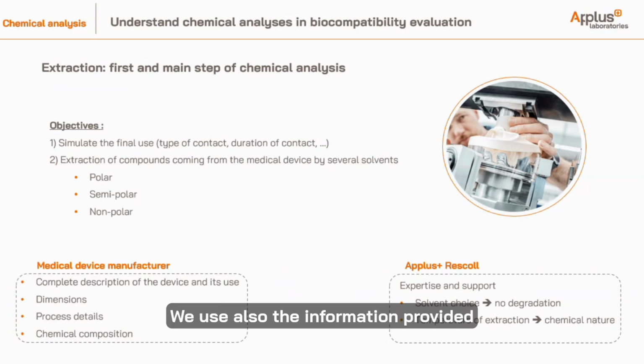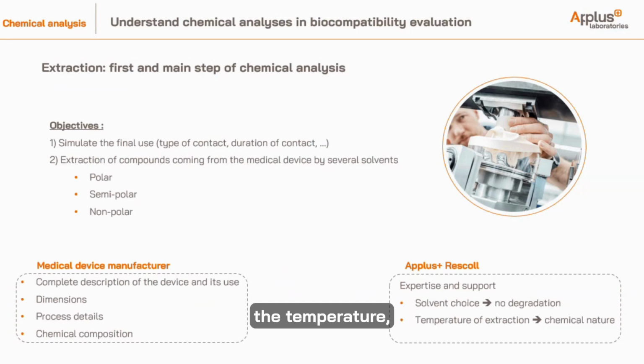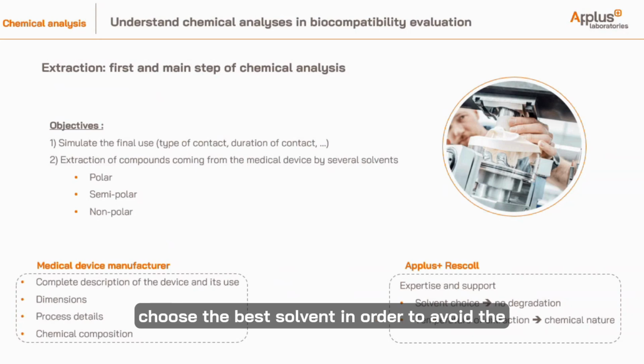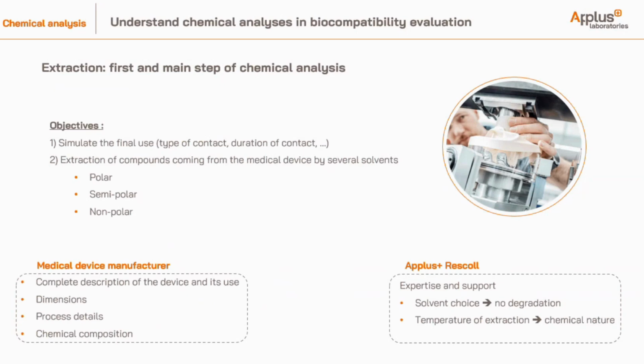We also use the information provided by the manufacturer on the type of contact and the duration of contact, as Marilys presented, to choose the extraction conditions, the temperature or the duration of extraction. So all information provided by the manufacturer can be important to determine the best way to perform extraction. And it can include dimensions of the medical device and a complete description of the device. The expertise of the laboratory is to choose the best solvent in order to avoid degradation of the medical device, and also to choose the temperature of extraction depending on the chemical nature of polymer medical devices.